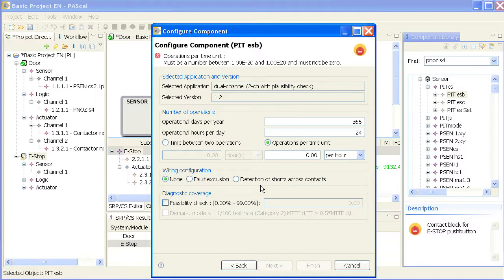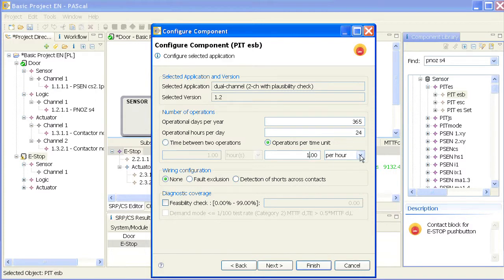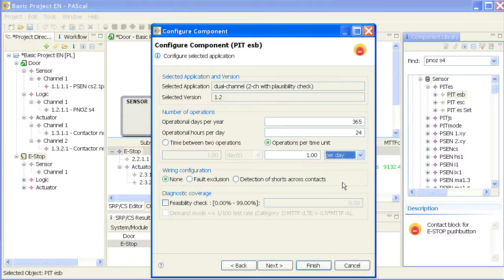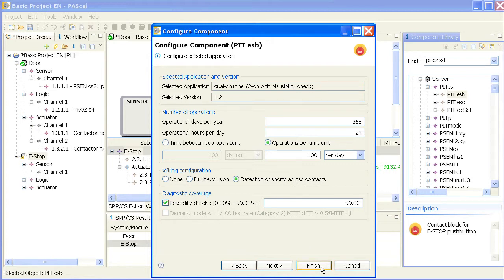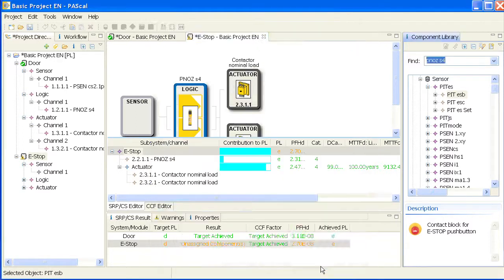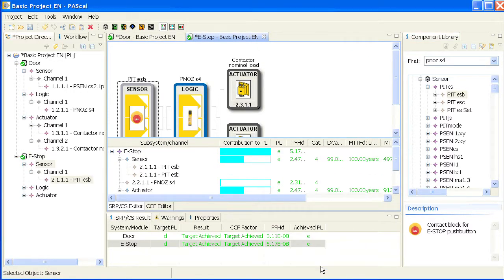The usability frequency. So here I have to enter how often the e-stop is activated. Once per hour, certainly too much. Let's say once per day. That's the time for the e-stop and I say the safety logic does a detection of shorts across the contacts and it does a feasibility check by monitoring the two channels and making sure that if one switches, we've got covered that the other may be faulty. So I replace it and my second safety function is done.